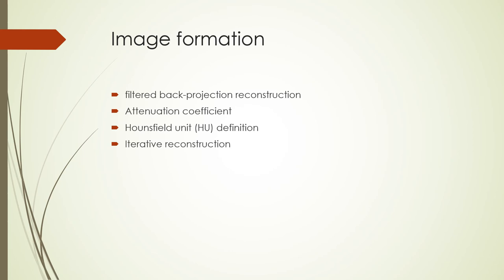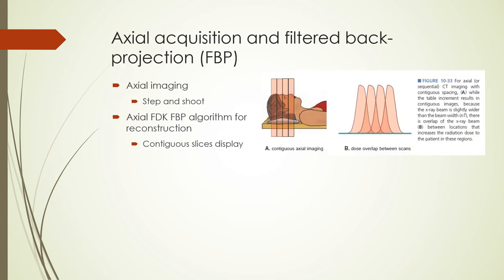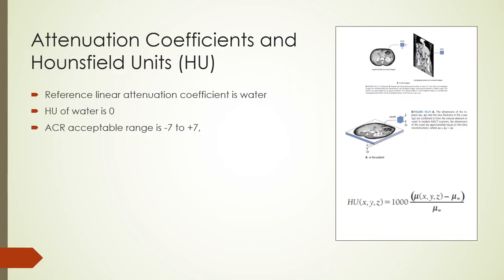After the patient is scanned, the image is reconstructed. Axial acquisition is a step-and-shoot mode; images are reconstructed using the Feldkamp-Davis-Kress (FDK) filtered back projection algorithm. Reconstructed images can be displayed with slice thicknesses between 0.625 mm and 10 mm in a contiguous manner with no gaps. Images are displayed with grayscale values called Hounsfield units, calculated from the linear attenuation coefficient of tissue in each voxel relative to water as the reference; the Hounsfield unit of water is on average zero.